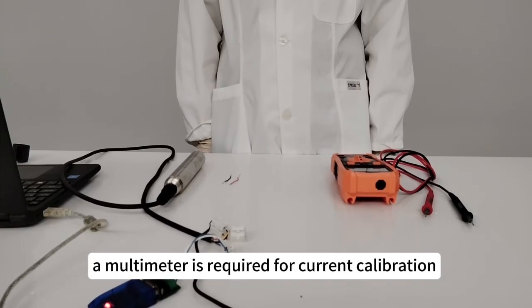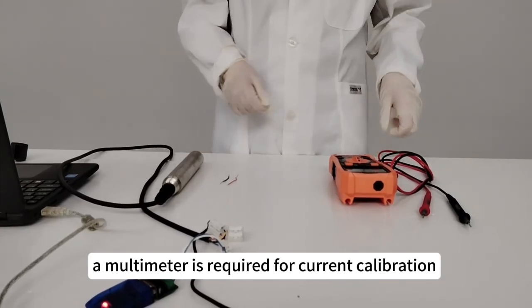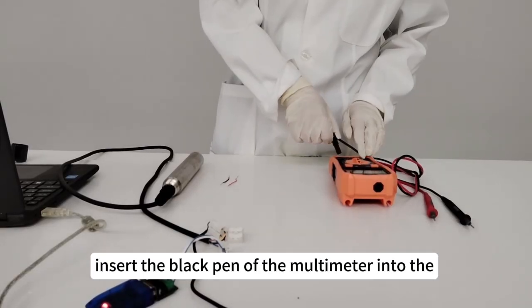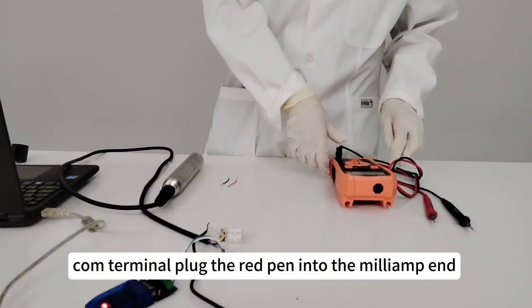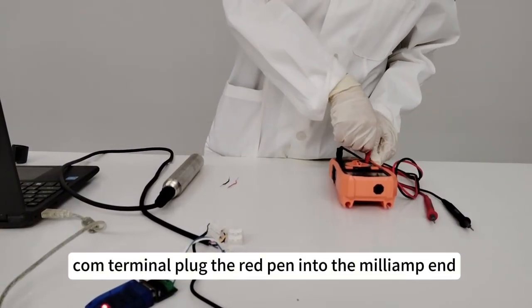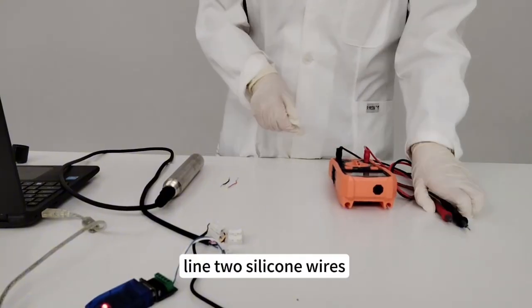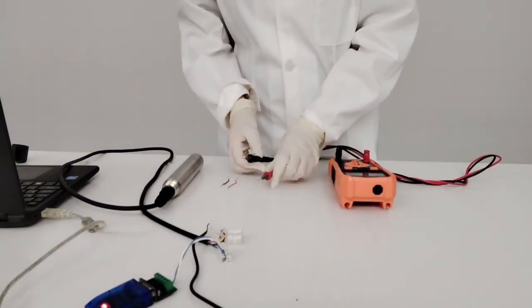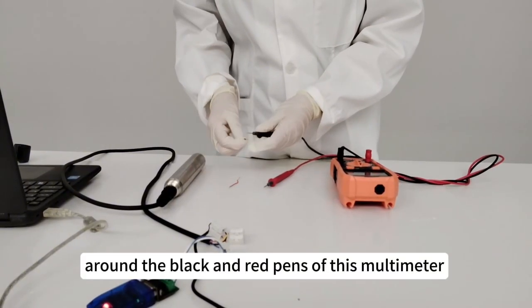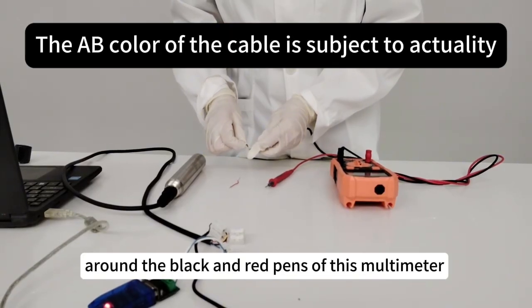A multimeter is required for current calibration. Insert the black pen of the multimeter into the COM terminal. Plug the red pen into the milliamp end. Find 2 silicone wires. Wrap them around the black and red pens of this multimeter.